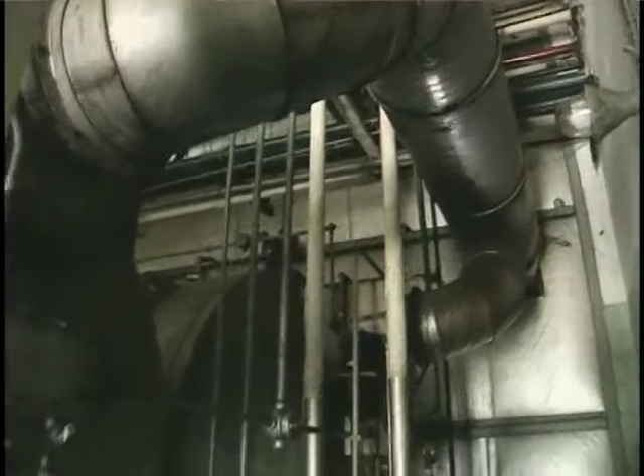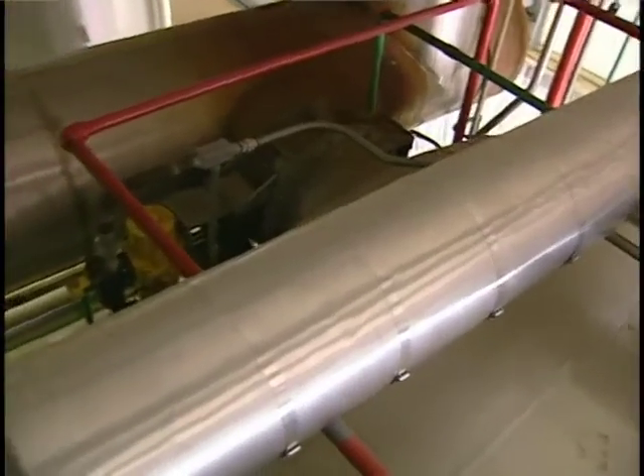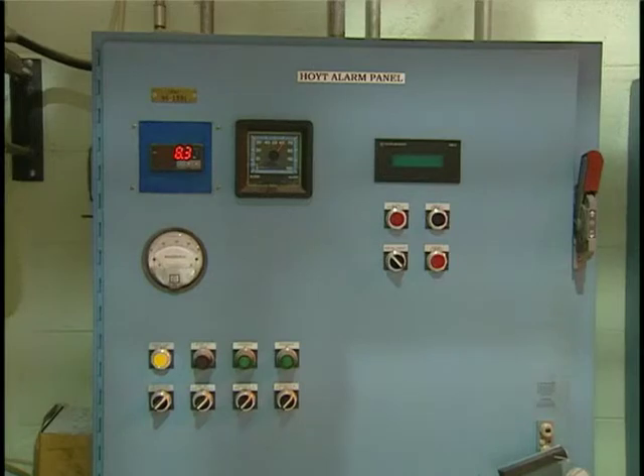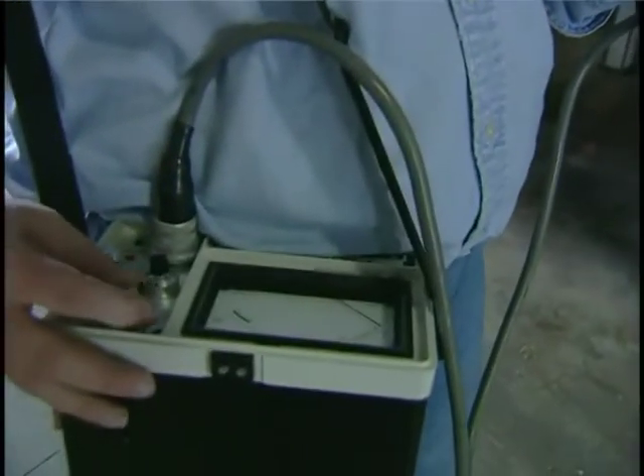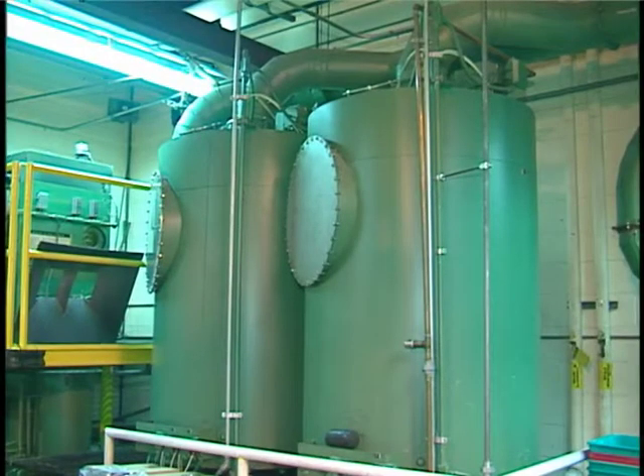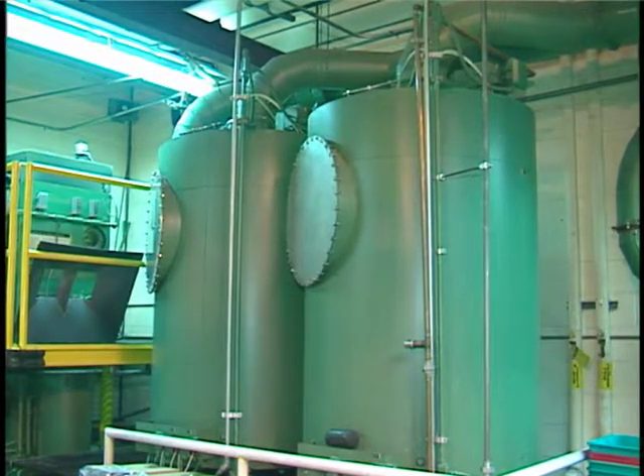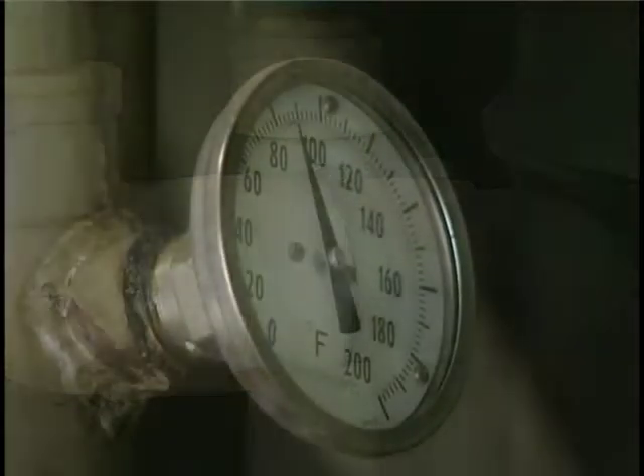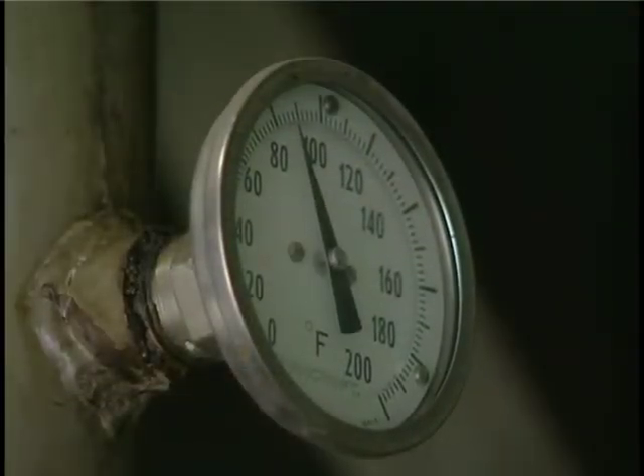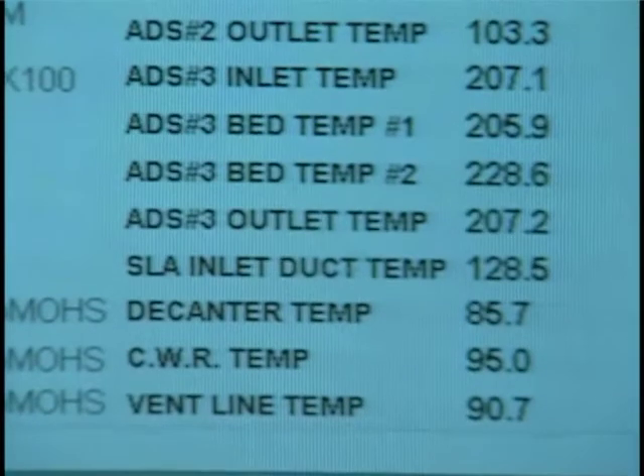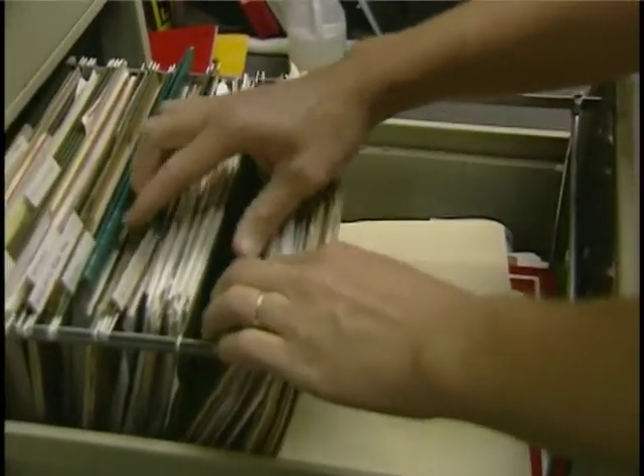The inlet concentration to the carbon adsorber should also be checked. Adsorbers designed to operate at 10 to 25 percent of the lower explosive limit will usually have an LEL monitor in the inlet duct to shut the system down if the concentration increases above this safety limit. Otherwise, the measurement will have to be made with a portable analyzer. Increased inlet concentration could lead to breakthrough unless the regeneration frequency has been increased. The inlet gas temperature is one of the most important variables affecting performance; increased gas temperature will substantially reduce the capacity of the carbon bed, leading to breakthrough. The current inlet gas temperature and historical temperature records over the last several months should be evaluated for significant increases above baseline values.